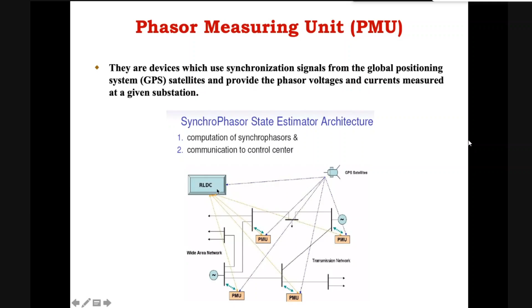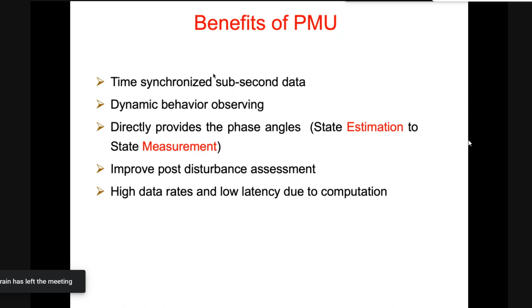So what is the benefit? This PMU will give time synchronized data. Earlier we used SCADA and DCS measurement in RLDC, and SCADA and DCS normally estimate the data, but here it is measuring the data.